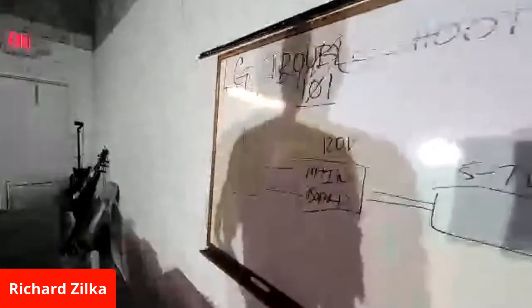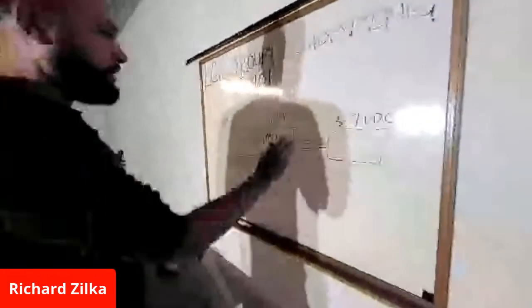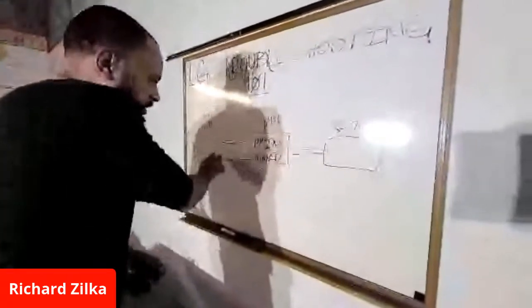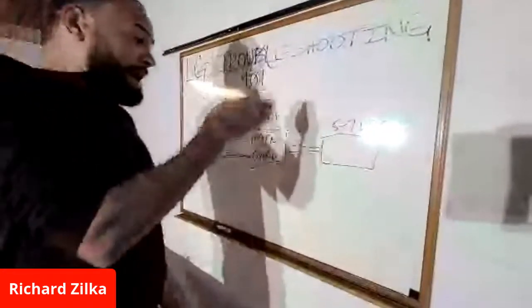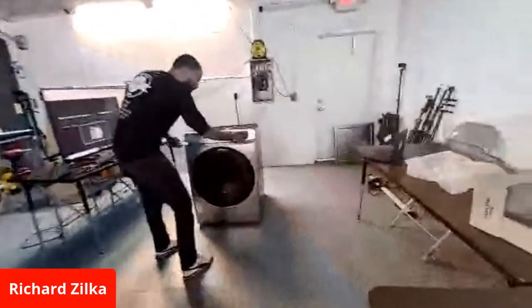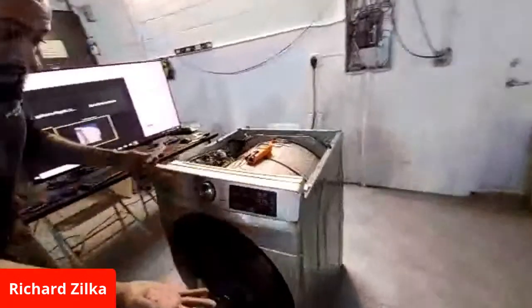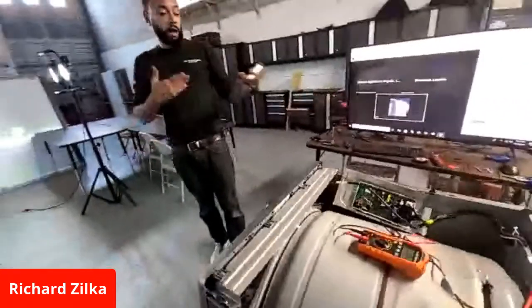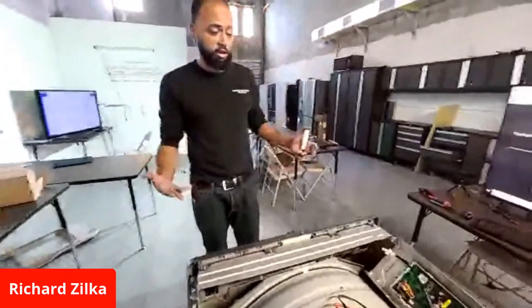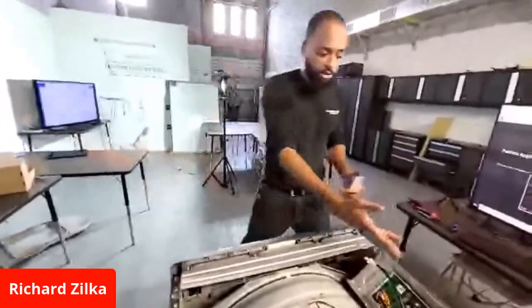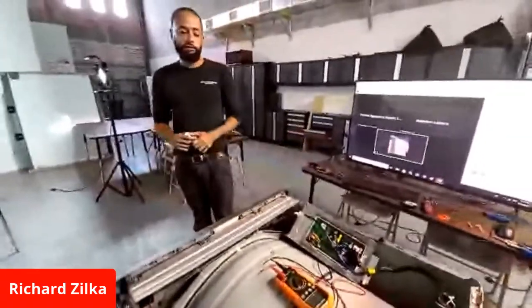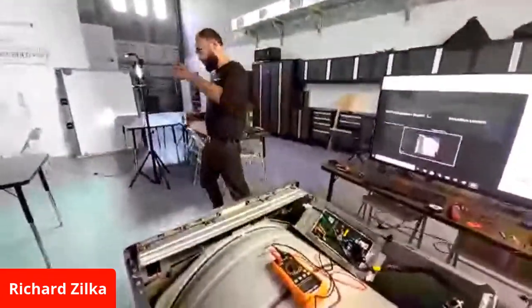We made sure we had 120, and we made sure we had 240. We checked from the dryer, from the terminal block, going to the board. We confirmed we had 120, which we did. But now we get to this guy right here, and we're not getting any action. Right away, the first response from the other guy who originally troubleshot this was, oh, it's the board. And that's what we went with. That's not how you do it.